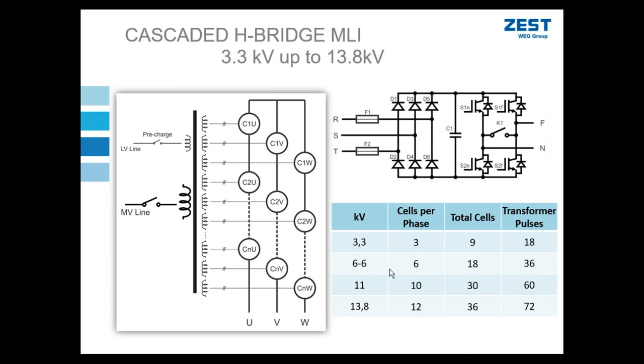For a 6.6 kV device or drive, I'm doubling my voltage now from 3.3 to 6.6. So it stands to reason I need to double my number of cells per phase from 3 to 6. And in total, my cells will double also from 9 to 18. And then I also need 18 secondary windings.